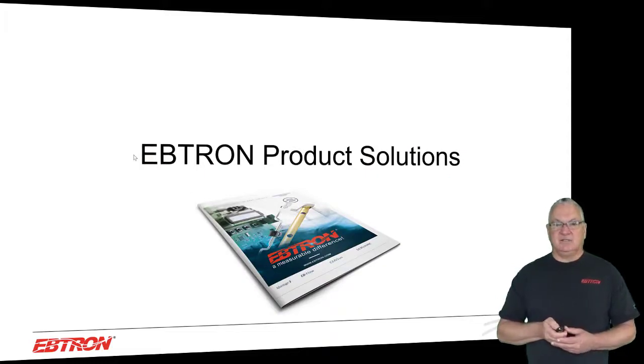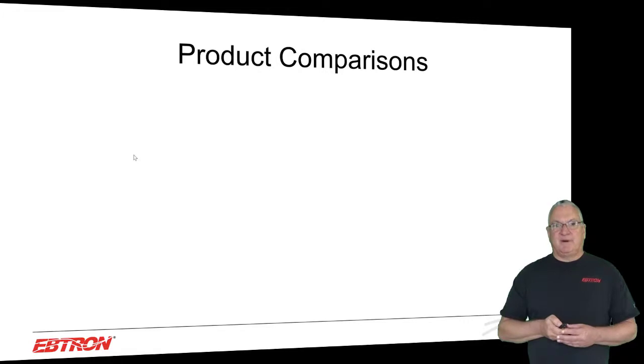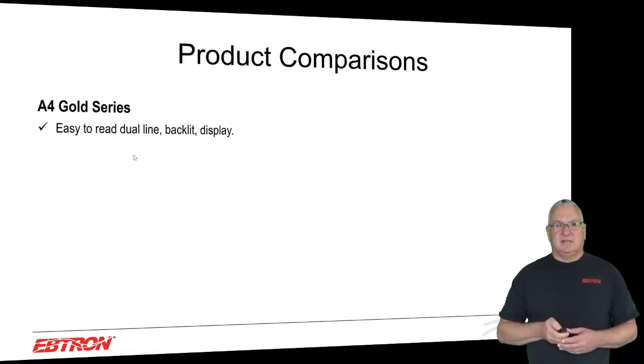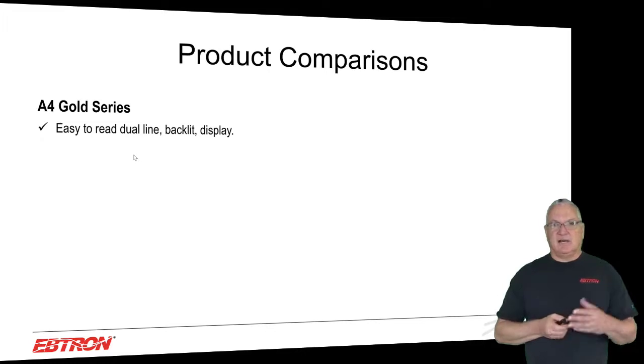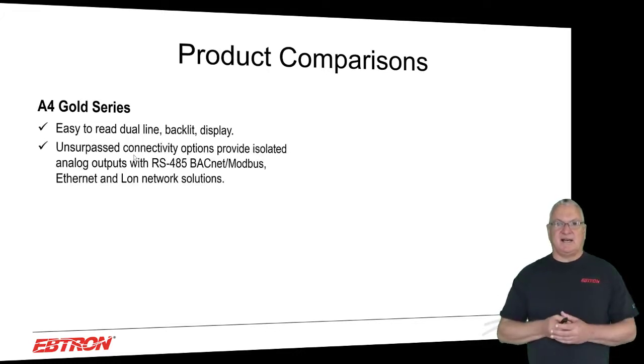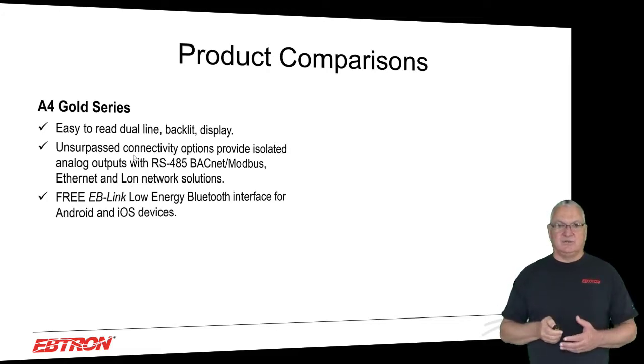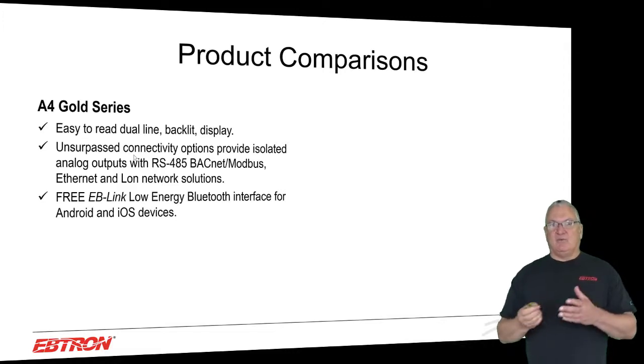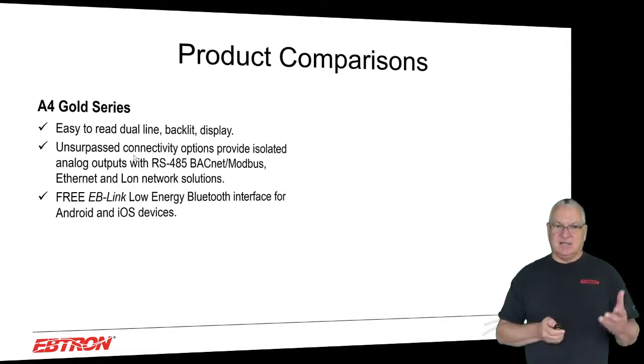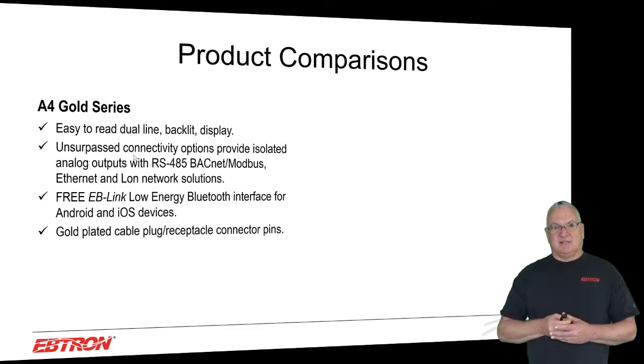In our product solutions, I'm going to go through this quickly. On product comparisons, we have our gold series. Basically, we've gone to this easy to read dual line backlit display. We have really unsurpassed connectivity options. We provide isolated outputs. We have RS-485, BACnet and Modbus, Ethernet and Lon network solutions. We provide you with, on the Gold series, a free low energy Bluetooth interface for Android and iOS devices. If you don't want that, we can provide it without the radio, but it is provided on the product unless you specify that you don't want it. All of the connector pins, as I said, are gold plated. Everything is gold plated, all connections, interconnects.